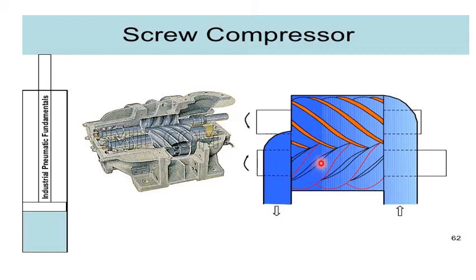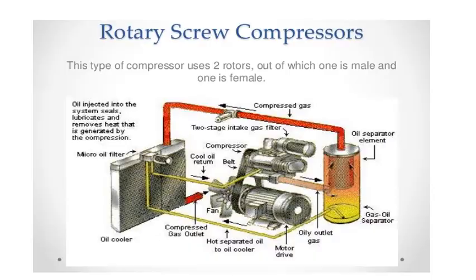The male rotor is the driver and the female rotor is the driven. The lobes exactly mesh with the gullies. The two rotors are in mesh with each other. There are no suction and discharge valves. The gap between the casing and rotor is called a pocket. The pocket size goes on reducing from the inlet towards the outlet.